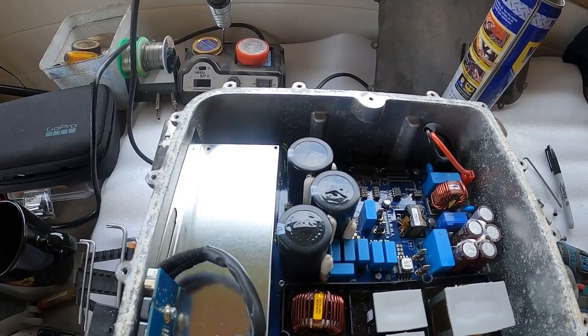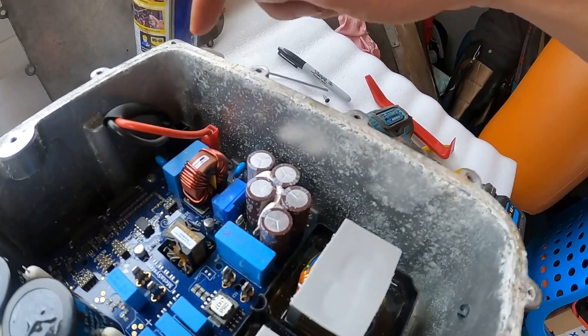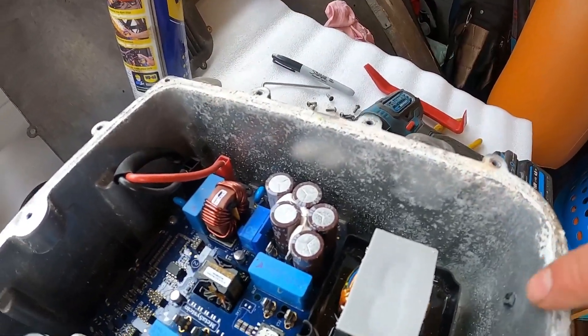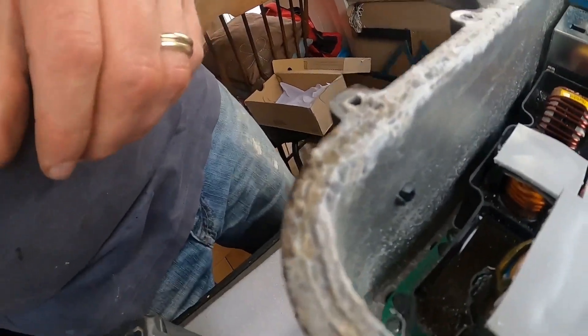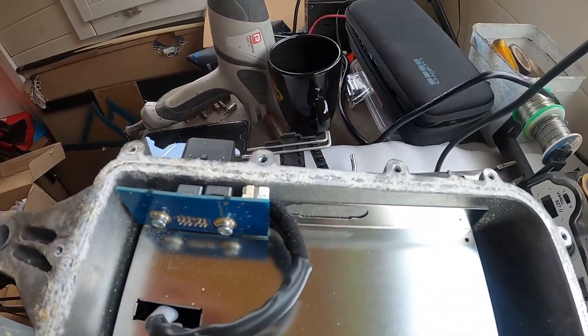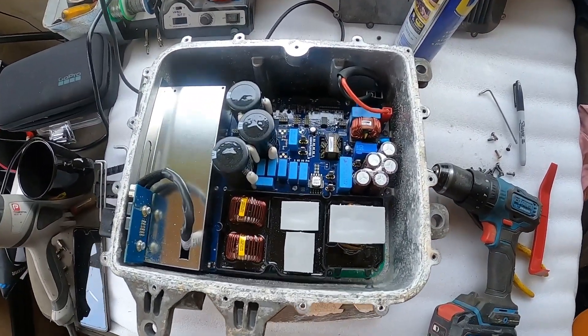So this is the KLE which is subject to a recall. We can see here how the corrosion is getting right on the inside of the unit — you can see it all down in there. So obviously the seal that was around there just wasn't doing its job. Right there, that's the inside of it all.